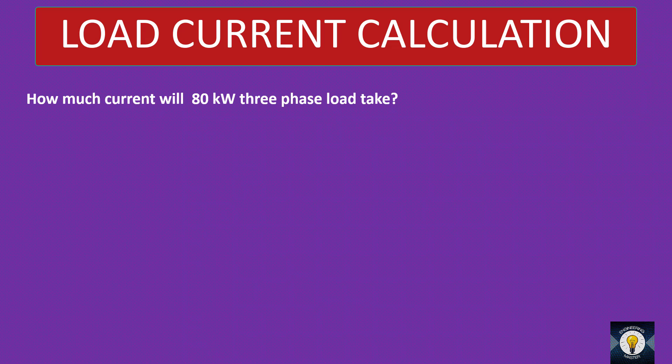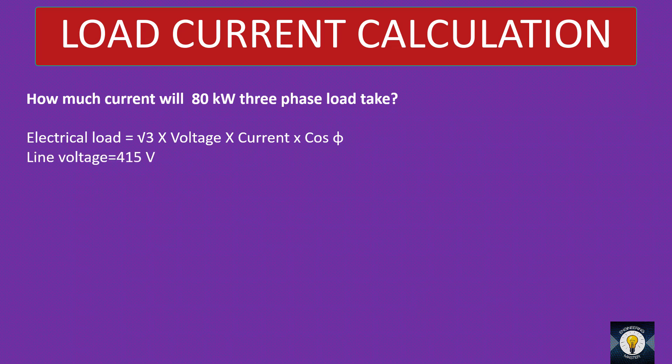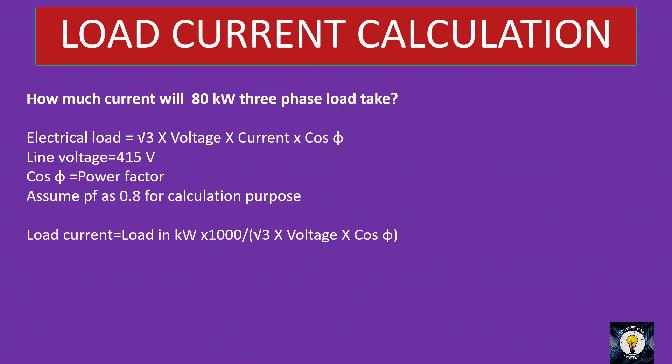Let's calculate the load current of an 80 kW three-phase load. The equation is: electrical load equals root 3 into voltage into current into cos φ. In three phase, voltage is line voltage — this may vary slightly from country to country, so take your local line voltage. My line voltage is 415 volt. Cos φ is the power factor — assume 0.8 for calculation purposes.